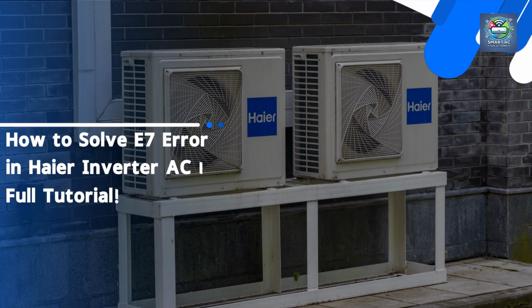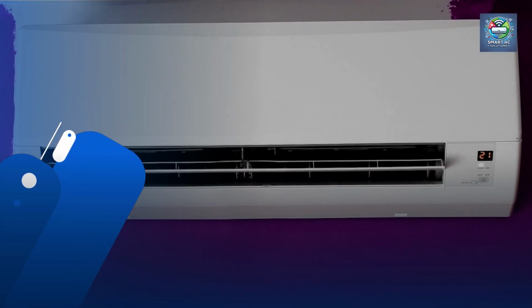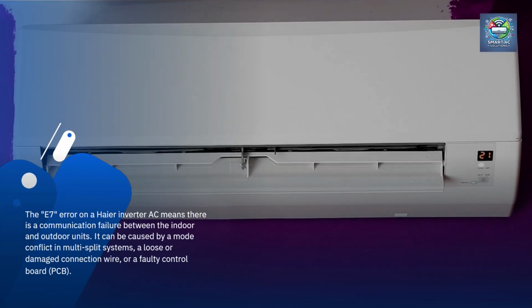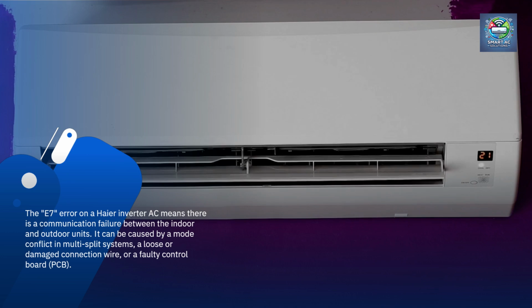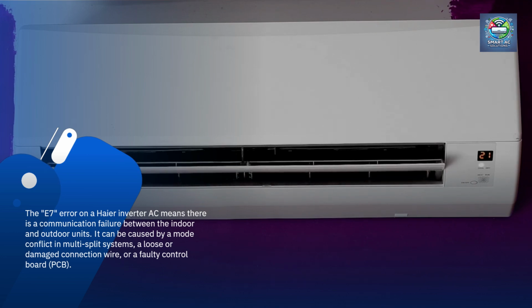How to solve E7 error in Haier inverter AC, full tutorial. The E7 error on a Haier inverter AC means there is a communication failure between the indoor and outdoor units.